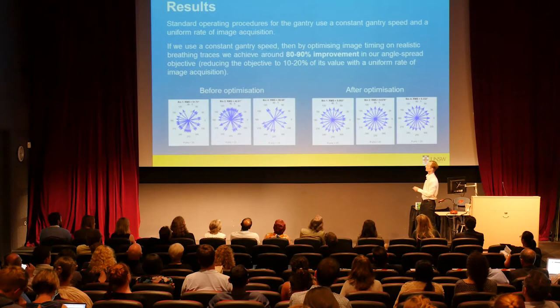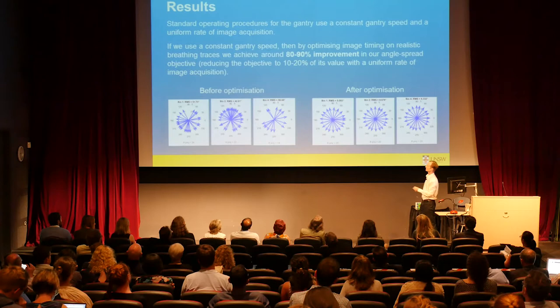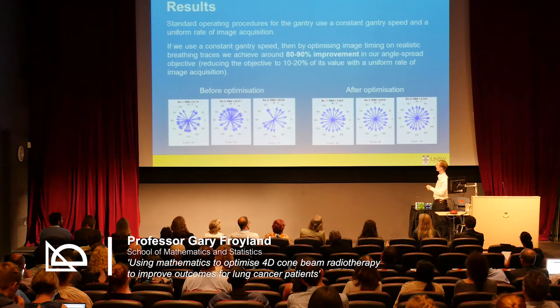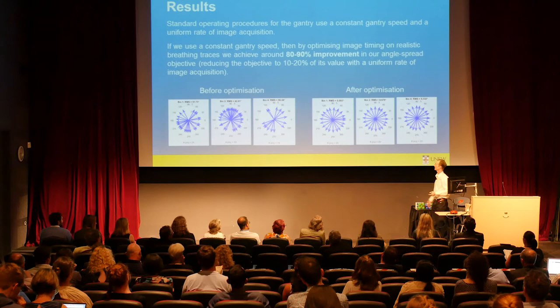Looking at the results: what's typically done is that, even though these are very fancy machines capable of all sorts of things, they often just cruise around at a constant rate and pulse every four seconds. This produces wagon wheels that are not particularly well spread and generates image artifacts like the streaks I showed. Just by retiming when you take the beams — even with constant gantry motion — you can get wagon wheels that are much better spread. This improvement is completely free: all you have to do is tell the machine to take a beam at a different time, and you get better images with nothing extra to buy.